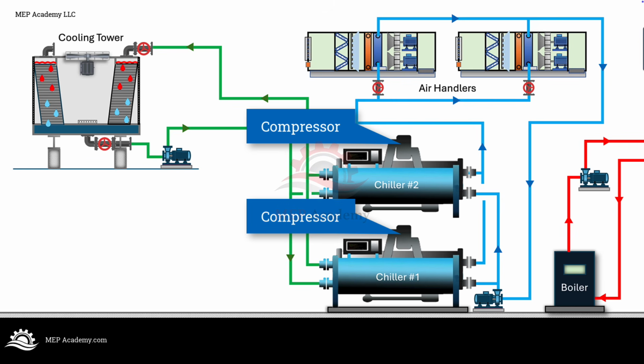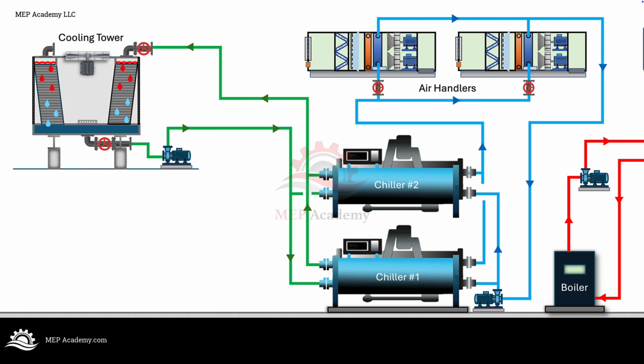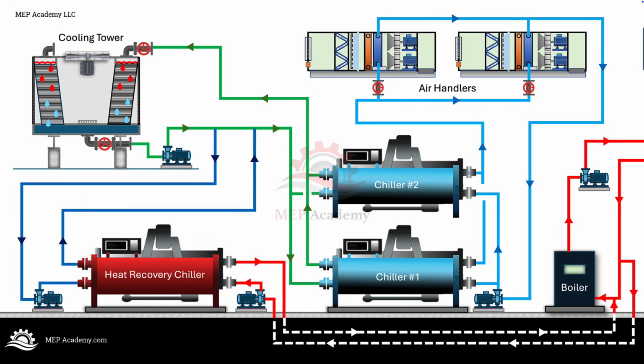The compressor does not have to work as hard, and the chiller can operate more efficiently, as long as the temperature stays within the manufacturer's allowable operating range. Now imagine adding a heat recovery chiller into this plant. The heat recovery chiller can be arranged so that it removes heat from the condenser water loop before that water feeds the main chillers. The condenser water enters the heat recovery chiller at a warmer temperature. The heat recovery chiller removes heat from that water. The condenser water then leaves the heat recovery chiller at a lower temperature and continues on to the main chillers.